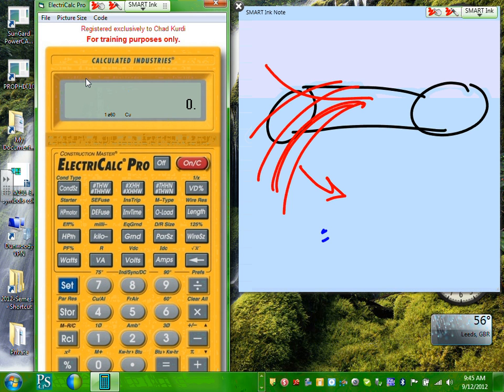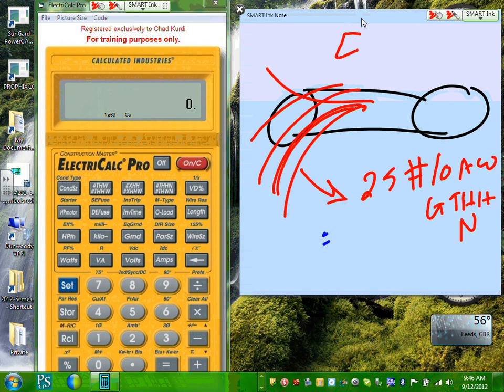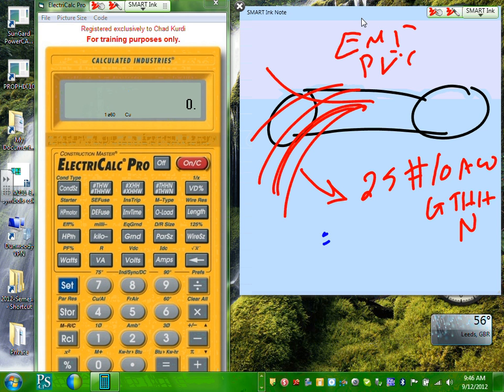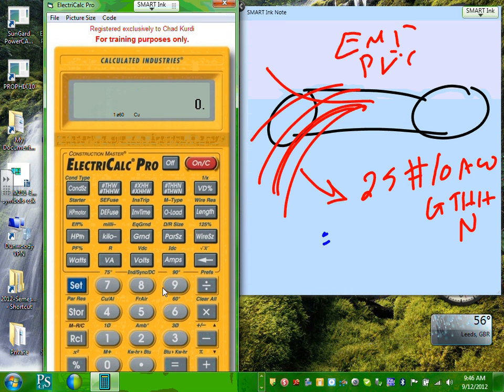Let's just say I have 25 number 10 AWG THHN in a conduit, and I need to use EMT and PVC. I want to size a conduit that can carry all these conductors, and first I want to try the EMT, and second I'm going to try the PVC. Okay, so 25. Here's how we do it. Let's start with the size of the conductor. What size conductor do we have?